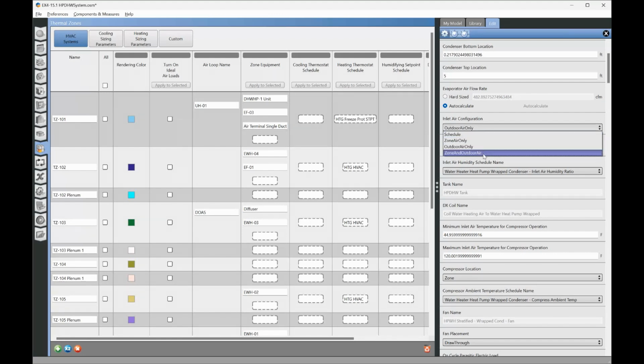And then you can do a combination of both of these, and we'll get into this a little bit later, but it's basically drawing a fraction of the air from the zone and a fraction of the air from the outdoors, and then it's exhausting it to the outdoors. So we are going to just do zone air only. So it's just going to be pulling air from our apparatus bay and exhausting it back to the apparatus bay. So it's going to be sort of cooling down our apparatus bay a little bit.